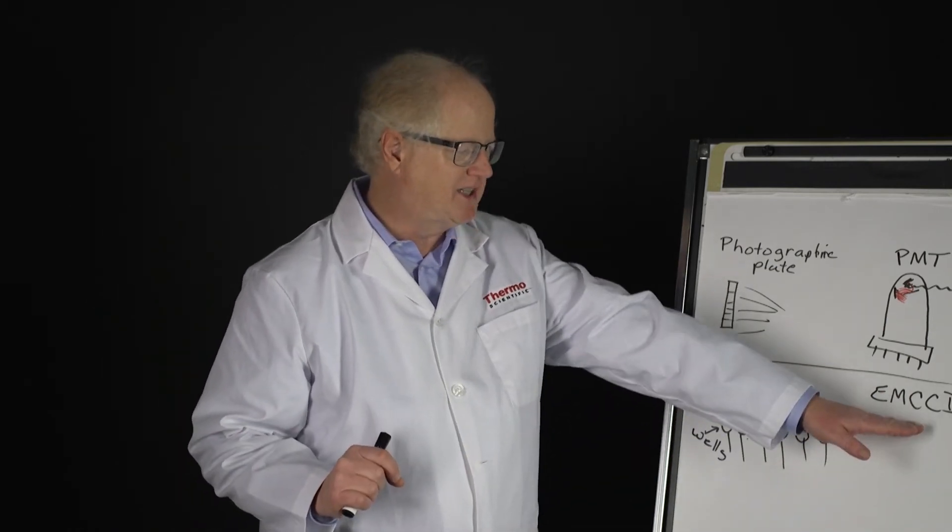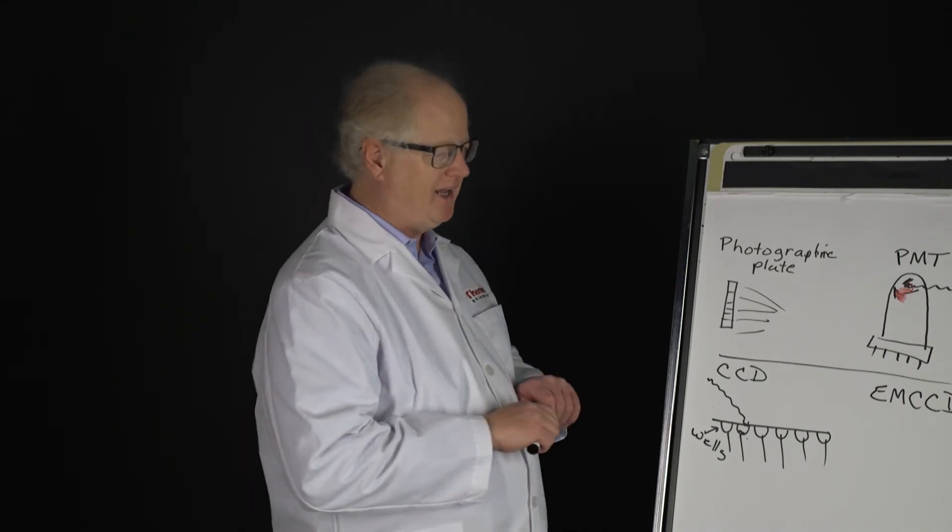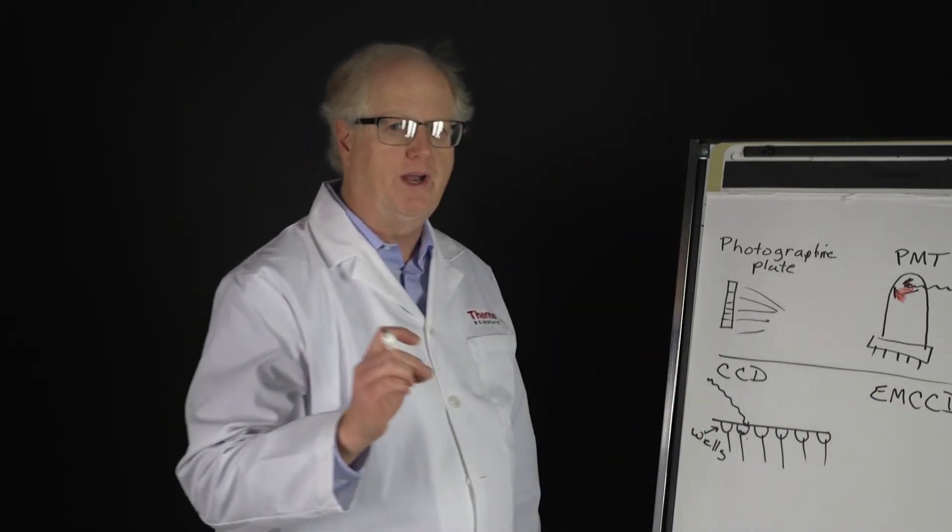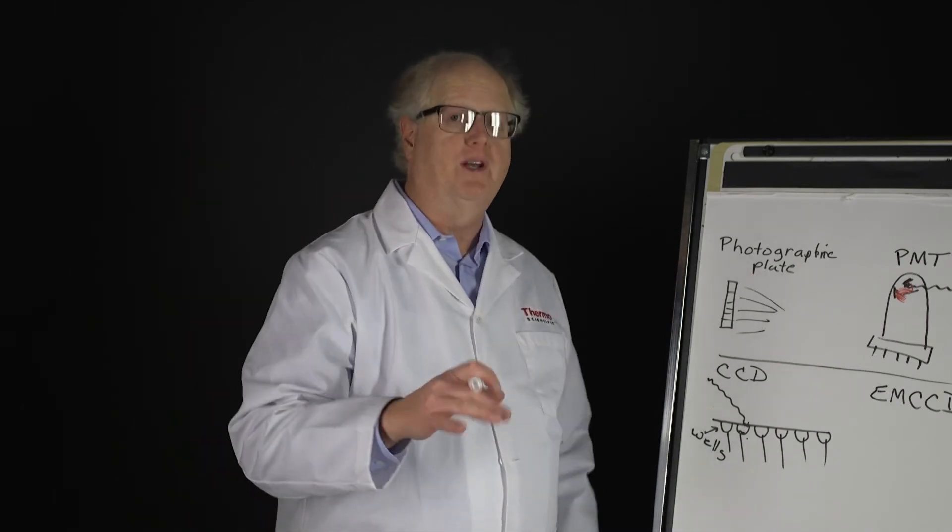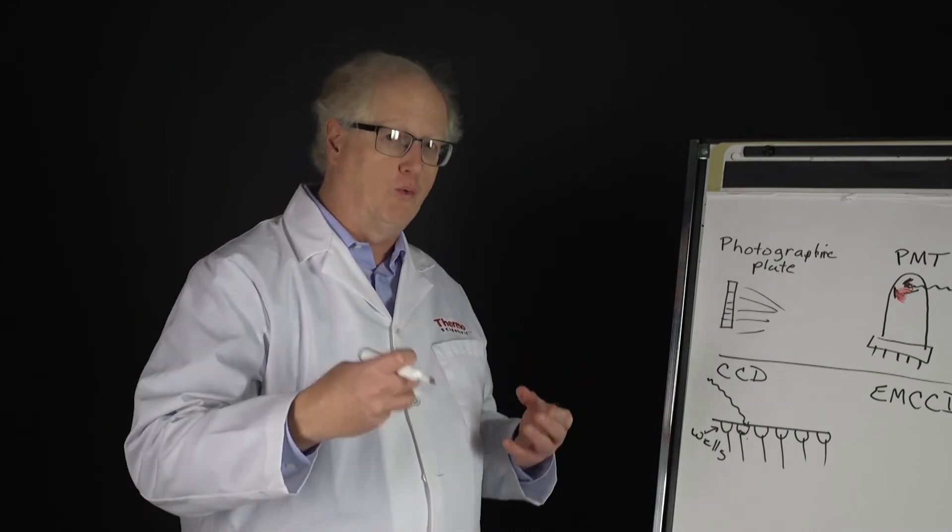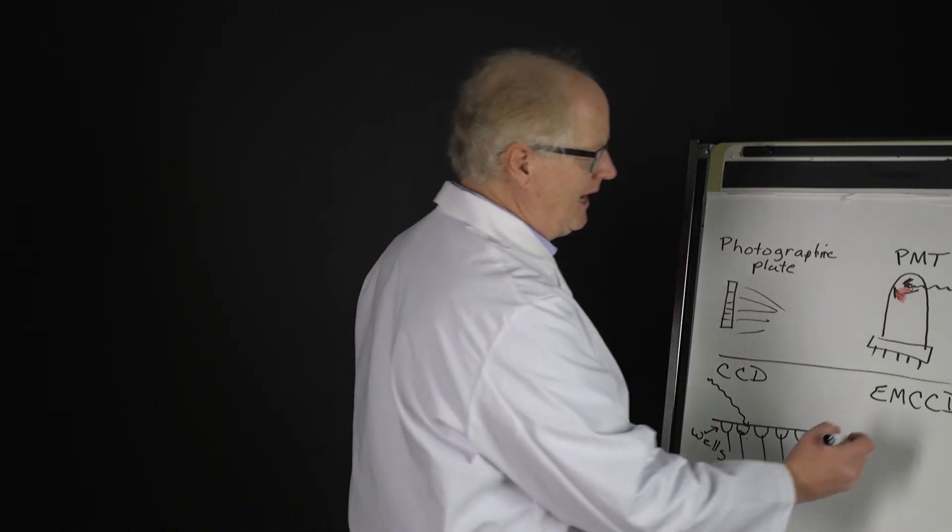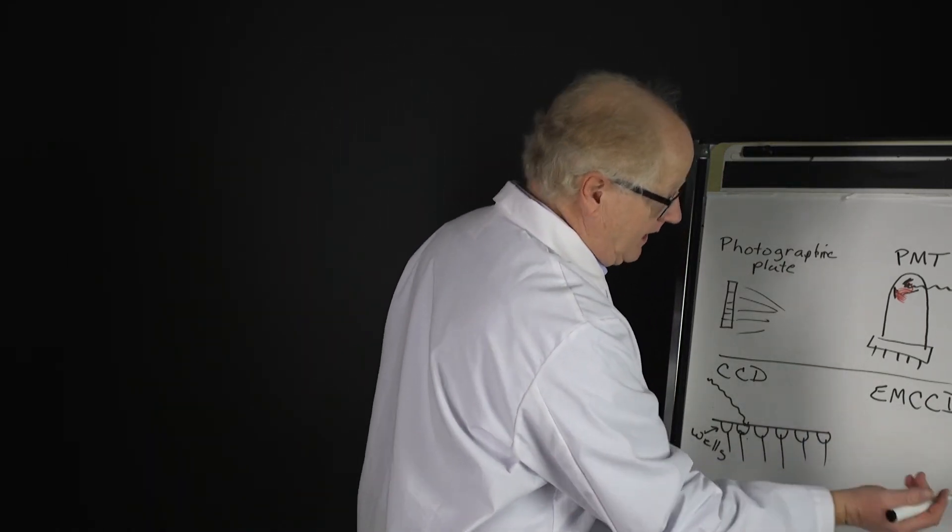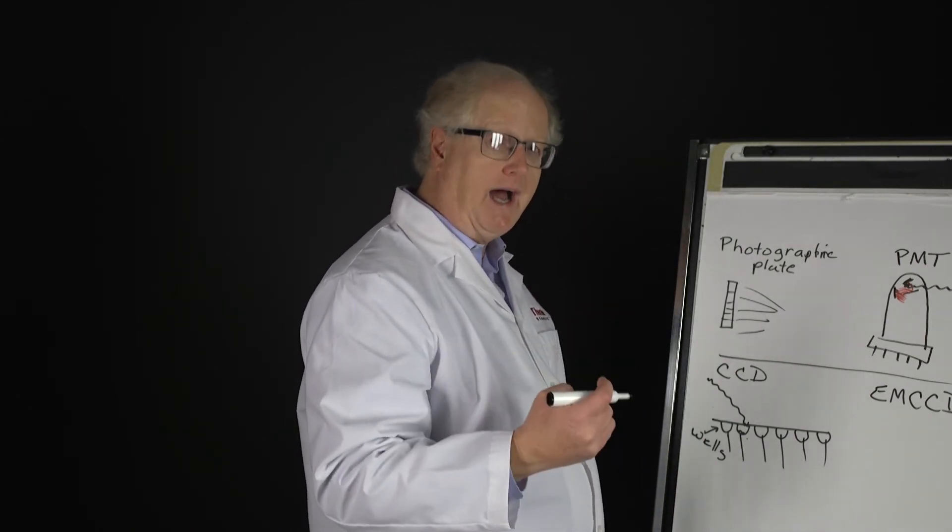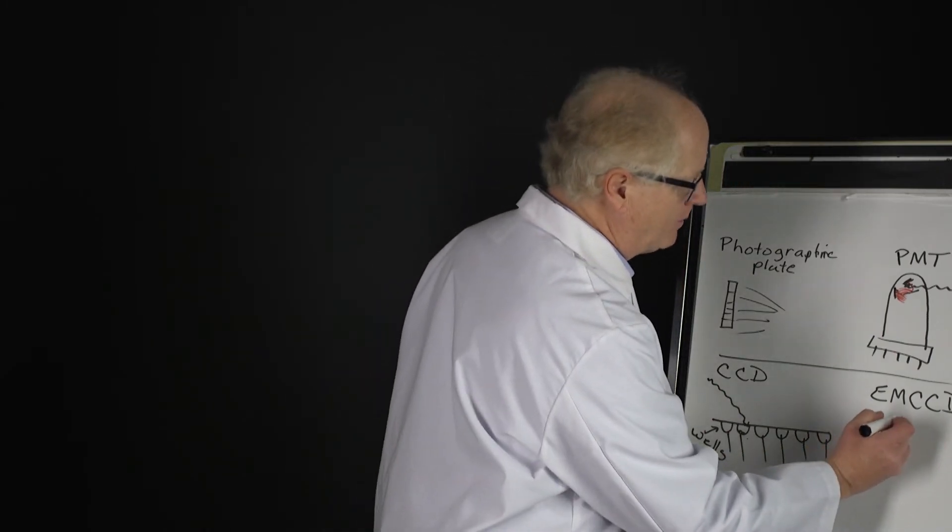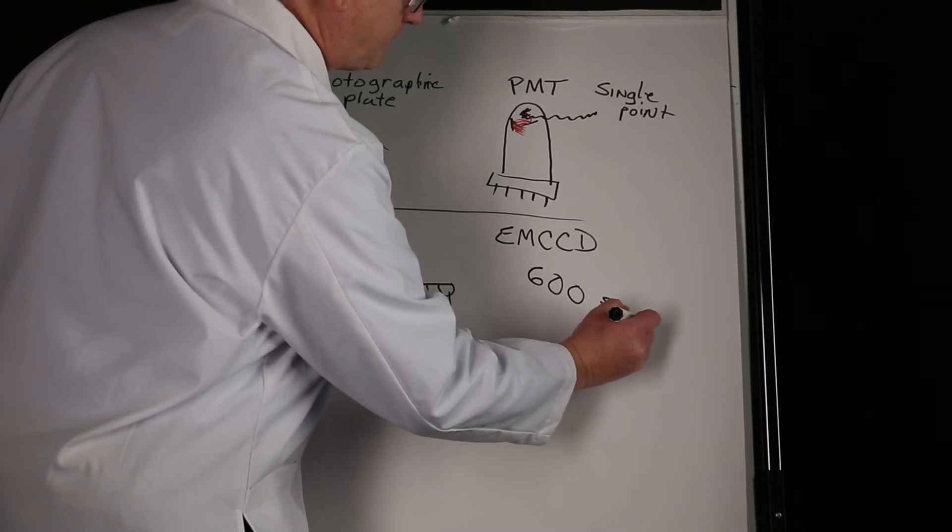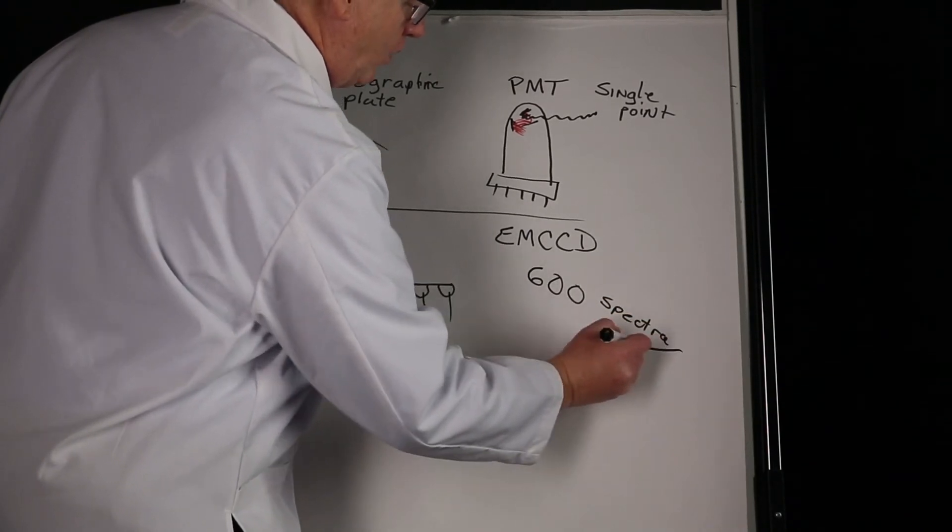The EMCCD is heavily used in high speed imaging purposes. The EMCCD by the nature of the way it works is able to collect that low light signal, amplify it, and then you can read it very quickly. This allows vendors to provide, as we do with our ThermoScientific DXR Xi imaging microscope, upwards of 600 or more spectra in one second.